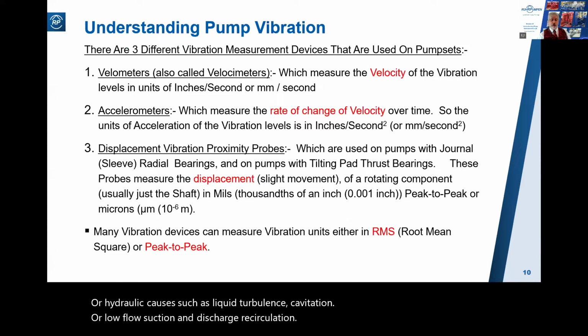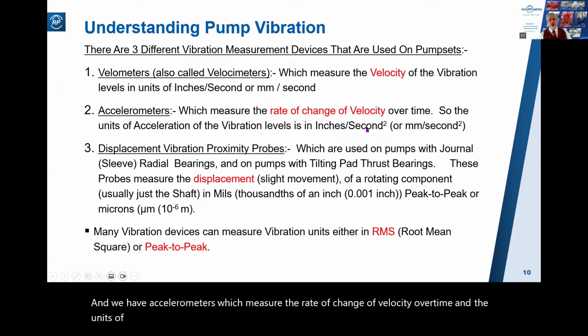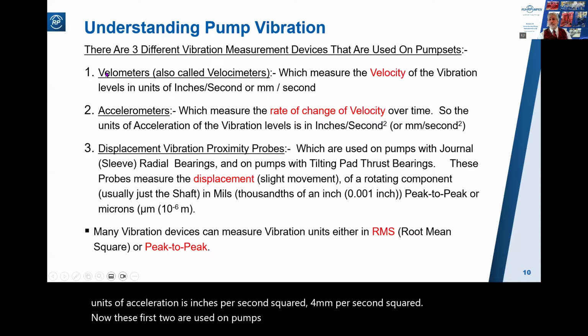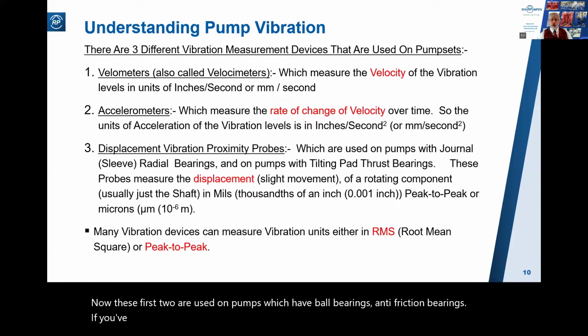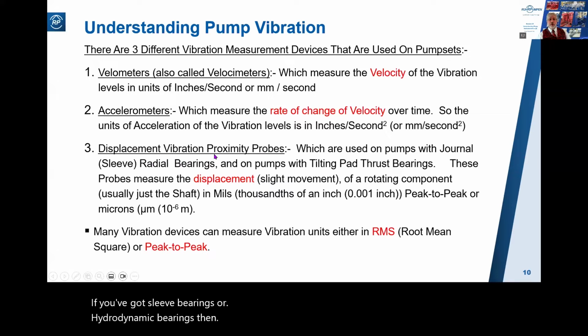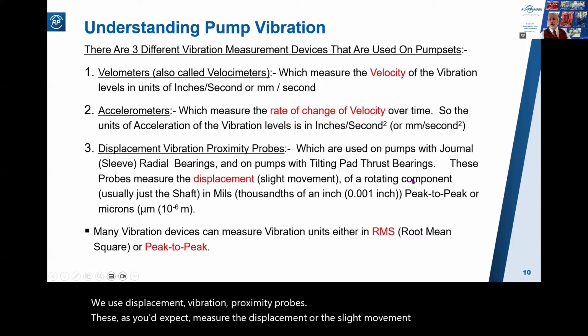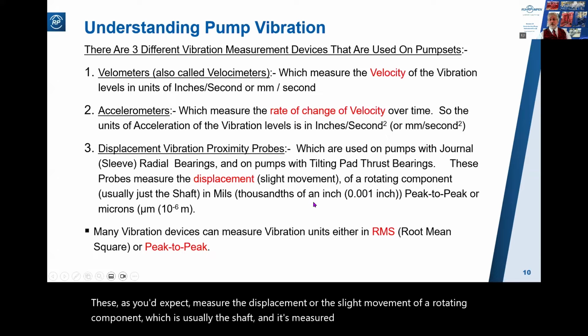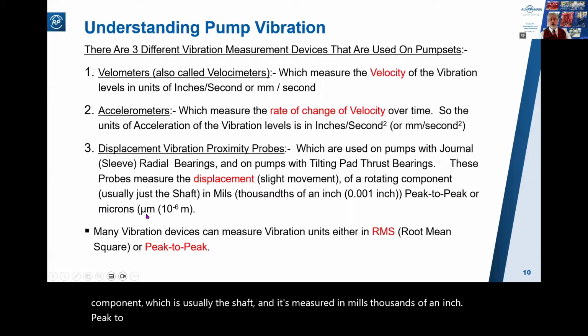And there are three methods of measuring the vibration. Velometers, which measure the velocity of the vibration levels in inches per second or millimeters per second. And we have accelerometers, which measure the rate of change of velocity over time. And the units of acceleration are inches per second squared or millimeters per second squared. Now, these first two are used on pumps which have ball bearings, anti-friction bearings. If you've got sleeve bearings or hydrodynamic bearings, then we use displacement vibration proximity probes. These, as you'd expect, measure the displacement or the slight movement of a rotating component, which is usually the shaft, and it's measured in mils, thousandths of an inch, peak to peak, or in microns, again, peak to peak.